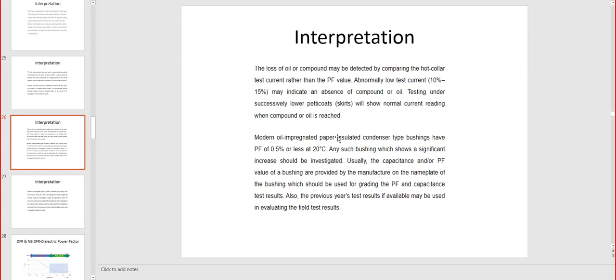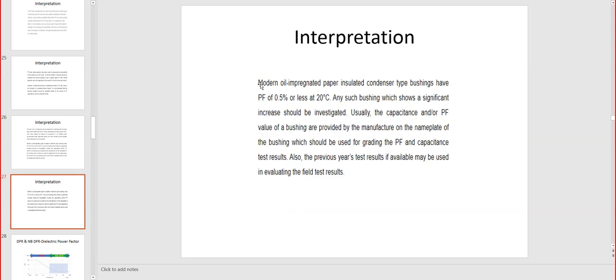Modern oil impregnated paper insulated condenser type bushings have power factor 0.5 or less at 20. Any such bushing which shows a significant increase should be investigated. Usually the capacitance or power factor of the bushing are provided by the manufacturers. We're going to see the nameplate data for our transformers. Another interpretation here, similar to the previous ones regarding the power factor.